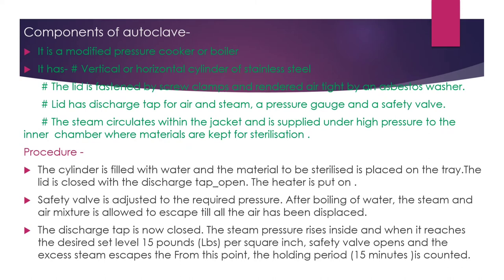Procedure: the cylinder is filled with water and the material to be sterilized is placed on the tray. The lid is closed with the discharge tap open and the heater is switched on. The safety valve is adjusted to the required pressure. After boiling, the steam-air mixture is allowed to escape until all air is displaced. The discharge tap is closed and steam pressure rises inside the autoclave to the desired level of 15 lbs per square inch, at which point the safety valve opens and excess steam escapes. The holding period of 15 minutes is then maintained.